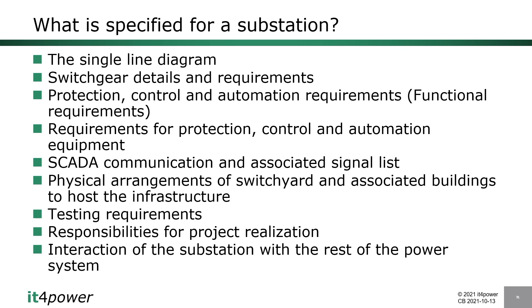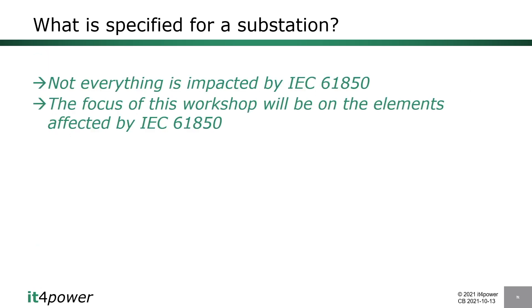For a 61850-based system where complete configuration is needed, you must define who is responsible for what in the overall project realization process. You also need to specify the interaction of the substation with the rest of the power system, including SCADA communication, interfaces to remote ends of power lines for line differential protection or protection acceleration schemes, and access from maintenance systems for remote upgrades or retrieval of disturbance records. A large amount of this is independent of 61850.